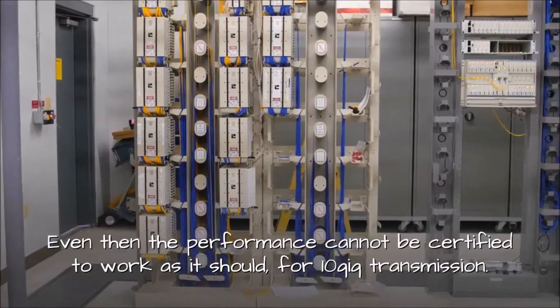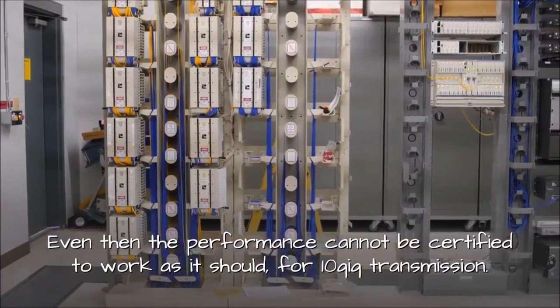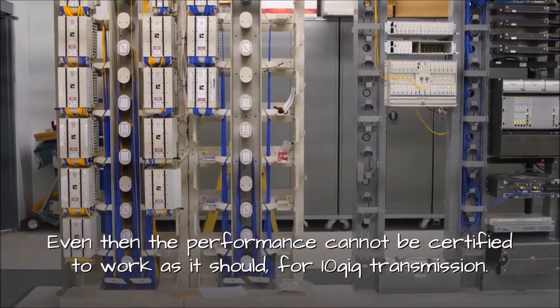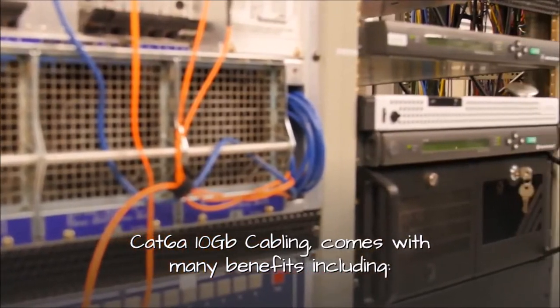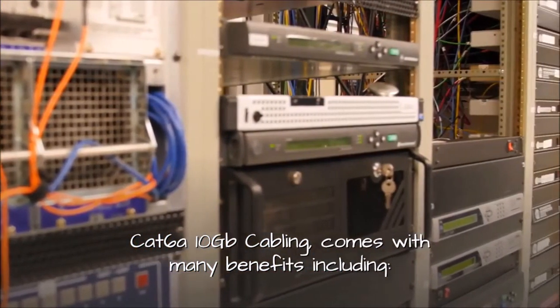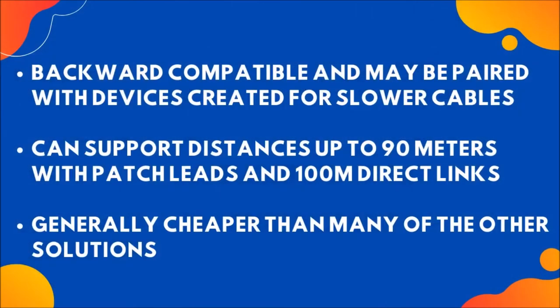Even then the performance cannot be certified to work as it should for 10 Gig transmission. CAT 6A 10 Gigabit cabling comes with many benefits including: backward compatible and may be paired with devices created for slower cables; can support distances up to 90 meters with patch leads and 100 meters for direct links; and is generally cheaper than many of the other solutions.